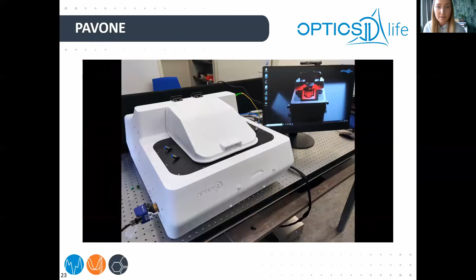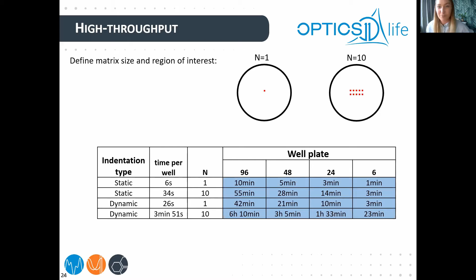Now, high throughput, so how high is the throughput? I put here in the table that if you want to do one static measurement in a well for 96 wells, it will take 10 minutes. If you want to perform a small matrix scan, it would take 55 minutes. So that is quite fast. Of course, for dynamic measurements, as you know, everything takes longer because you have to wait for this longer relaxation.